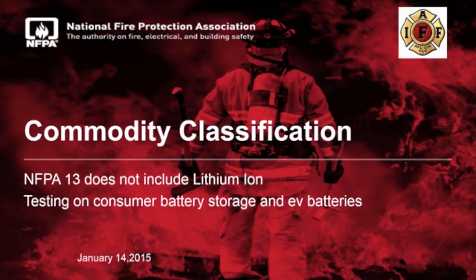Critical to understanding energy storage systems is commodity classification. Within the codes and standards environment, this is fundamental to NFPA, because NFPA 13, the standard on fire sprinkler systems, refers to commodity classification as the first step in determining the appropriate type of fire suppression sprinkler system for an occupancy.